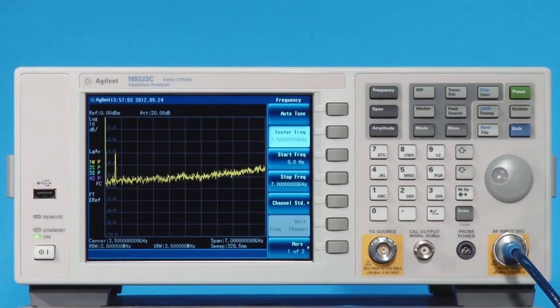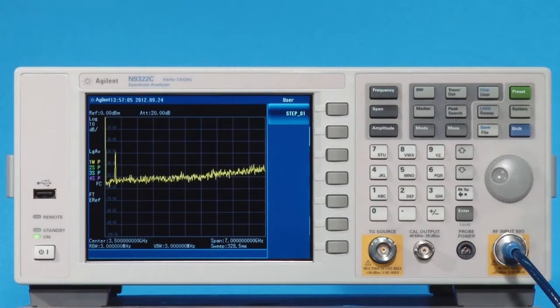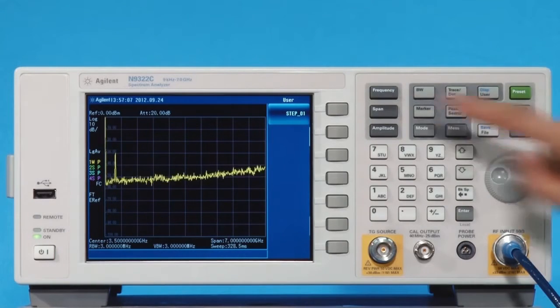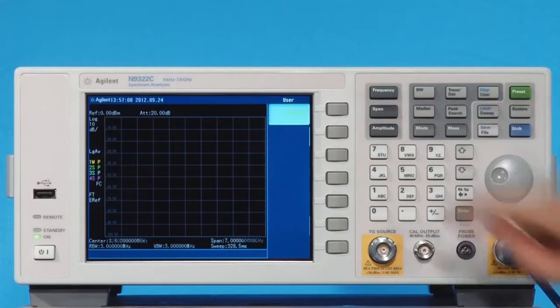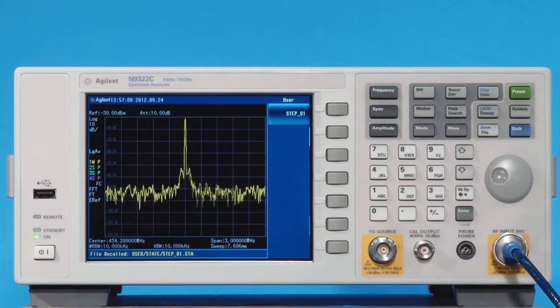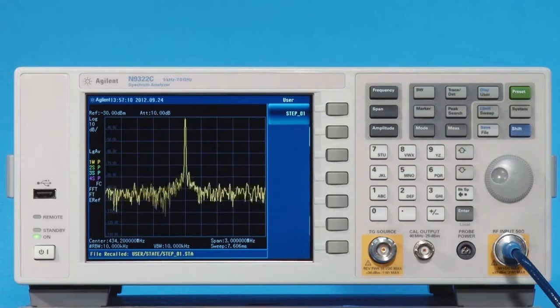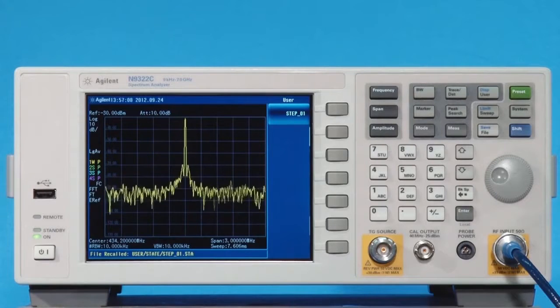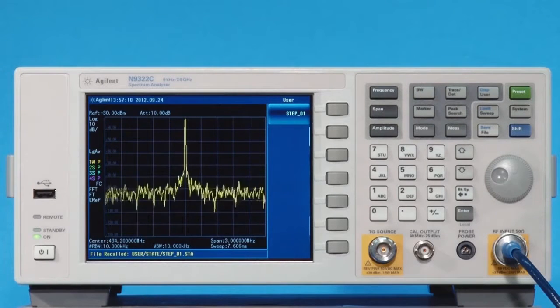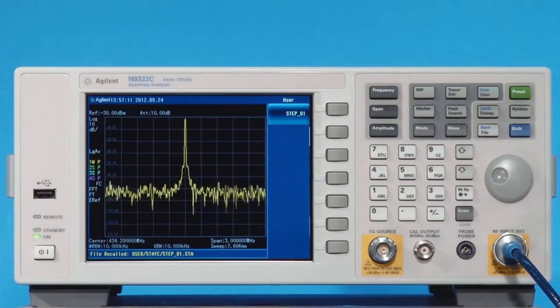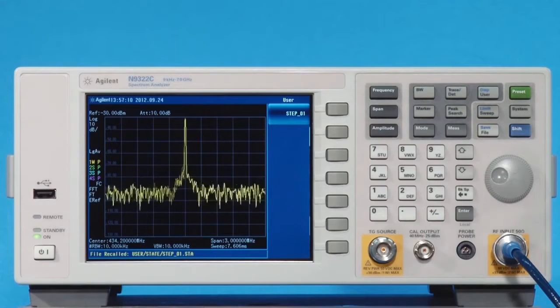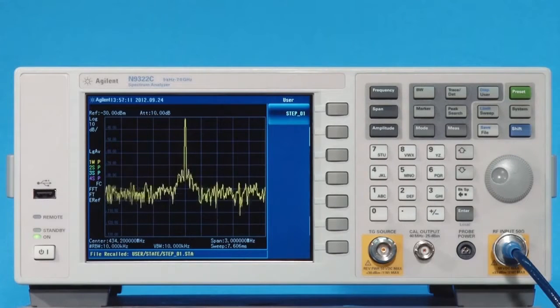Now, when you press the user key, you will see the step underscore 1 soft key. When you press step underscore 1, the analyzer will immediately recall the state file and set up all the parameters for measurement. This is very helpful for operators who have to implement repetitive tasks and reduce their time to set up the parameters.